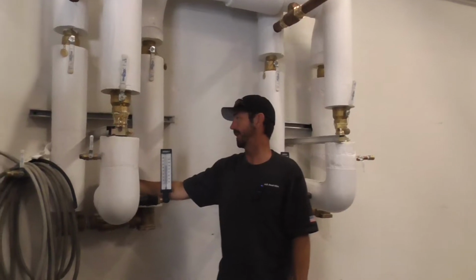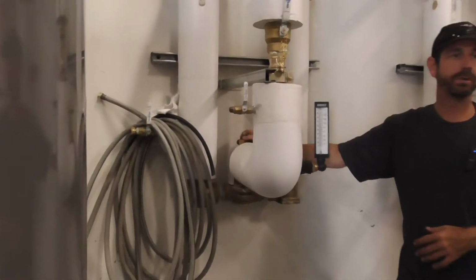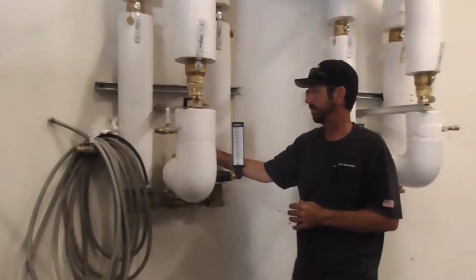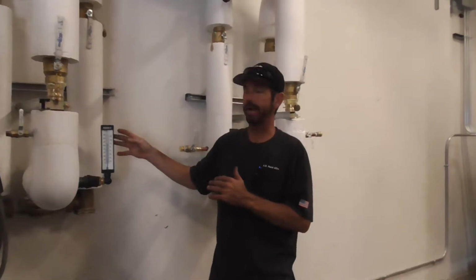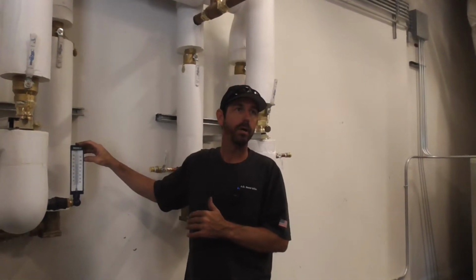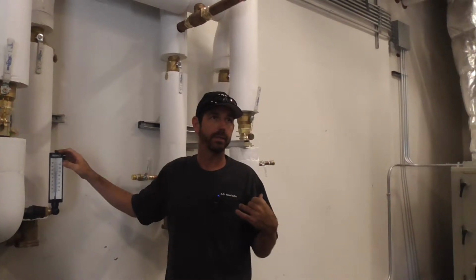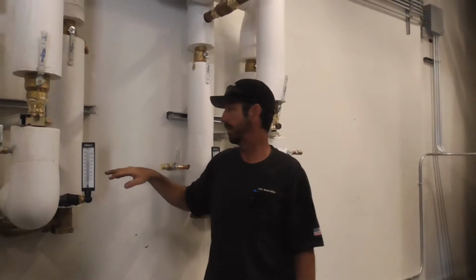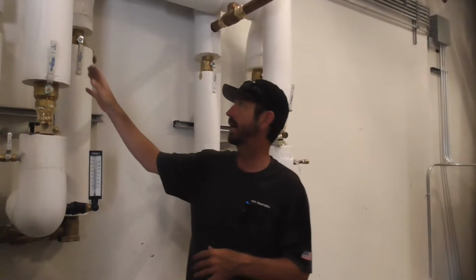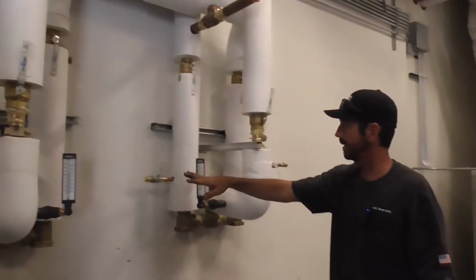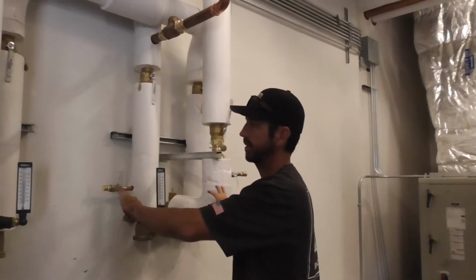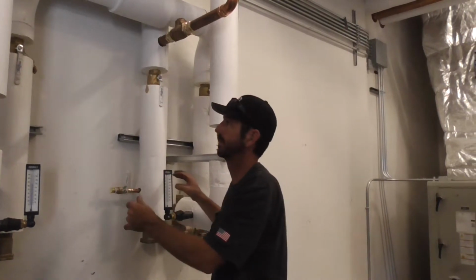That setting is adjusted by this up here. These do require maintenance. I would say quarterly again, inspect them. Just know, like right now this temperature is a little below, but we don't know the loading of the building right now. And then we don't know if the circ pump's running yet, okay? So we'd have to create a load to know if we're reading right, okay? So we can do that here by closing this valve. We have redundant mixing valves, okay? These are in parallel with each other, so you can service one and have some capacity to the building.